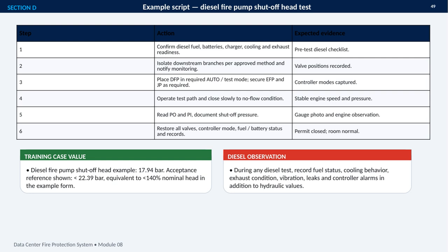The diesel fire pump is placed in the required automatic or test mode, while the electric and jockey pumps are secured as required. The test path is then operated, and the valve is closed slowly until a no-flow condition is reached. At that point, the presenter records both the suction and discharge pressure readings, along with stable engine speed and pressure. The example lists a shutoff head of 17.94 bar, with an acceptance reference below 22.39 bar, or below 140% of nominal head in the example form.